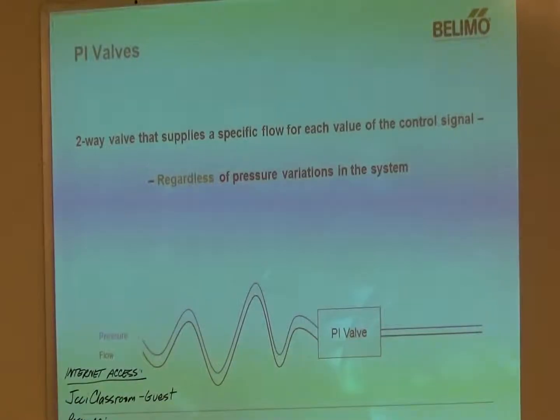So say you're at 6 volts. So over a 10 volt range, that's 50%. You're going to get 50% of the rated flow of that valve whenever you're at 6 volts.